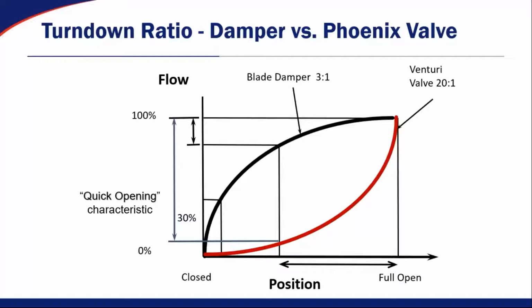And also when you get down into the low end of the airflow range, the accuracy is going to get much worse just based on the velocity pressure in the ductwork. Now, if you look at that red line, that is indicative of how a Phoenix Controls Venturi valve works. It's basically an inverse of the flow curve that you would have with a traditional VAV box. And again, that's because it's a completely different technology using Bernoulli's principle and the Venturi design inside the valve. Pressure does not affect how the Phoenix Controls accuracy works.